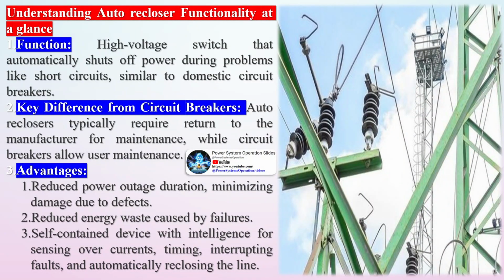Reclosers are designed to handle a short close-open duty cycle, where electrical engineers can optionally configure the number of attempted close operations prior to transitioning to a lockout stage. Reclosers are often used as a key component in a smart grid, as they are effectively computer-controlled switchgear which can be remotely operated and interrogated using SCADA or other communications. This isolation followed by re-energization process is exactly what an auto-recloser does.